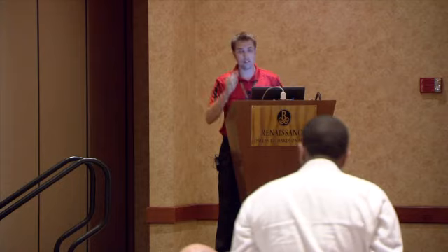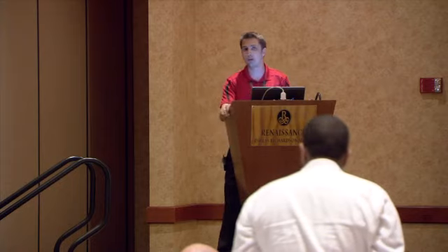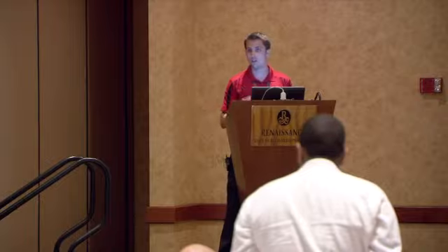Again, this is where it gets a little complicated. Rather than having a percentage, we don't actually have a good equation to just calculate what this preload register needs to be. It's a tough one to figure out, so you just increment and decrement it and narrow in on that value. As long as you keep this between 1 and 256, you're not going to mess it up. We found earlier that you have to knock this down a little bit, pretty high at first, since we're using such low values. So mine is negative 100 I'm going to start with. I'm going to put this phase value down at about 123. You enter that and update meter, and it went down to 123.